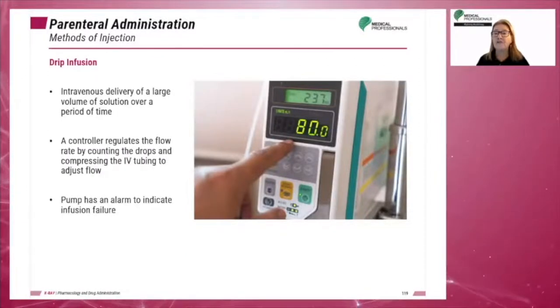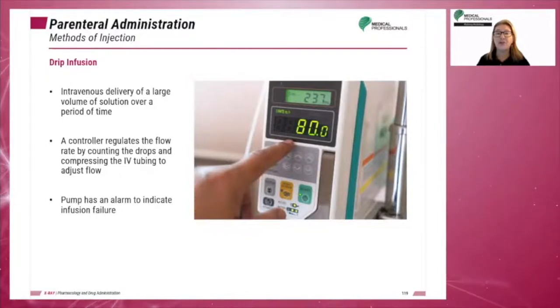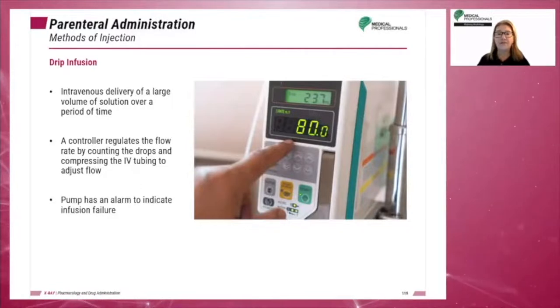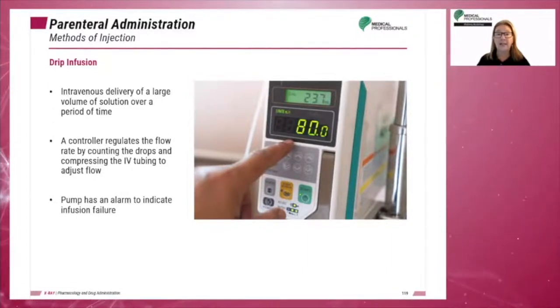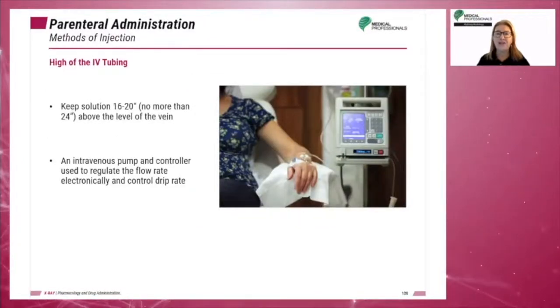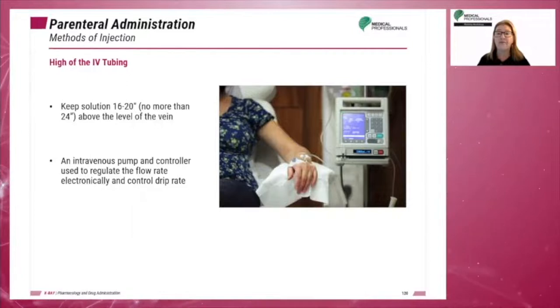Drip infusion involves slowly dripping or infusing the medication into the patient. This method is used to deliver a large volume of solution intravenously over a period of time. The equipment needed is an intravenous pole and an infusion set. In the infusion set, a controller regulates the flow rate by counting the drops and compressing the IV tube to adjust flow. The pump has an alarm to indicate infusion failure. The medication in a drip infusion set should be kept no more than 24 inches above the level of the vein.